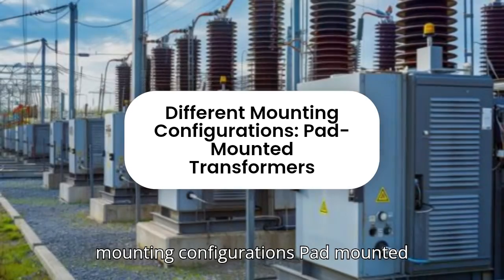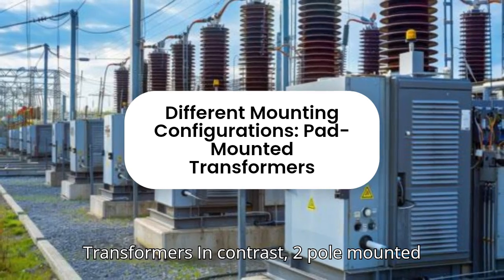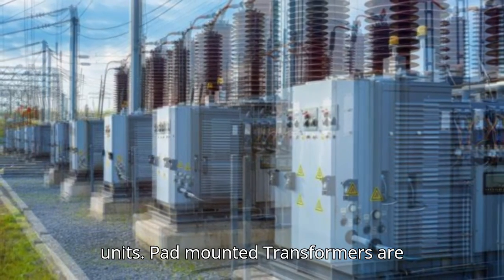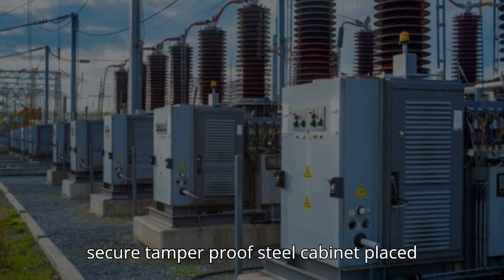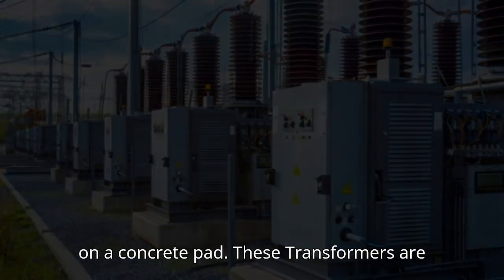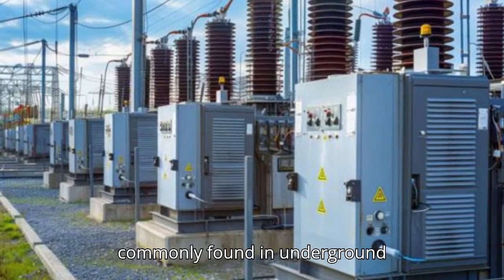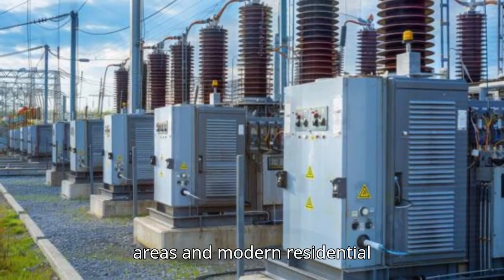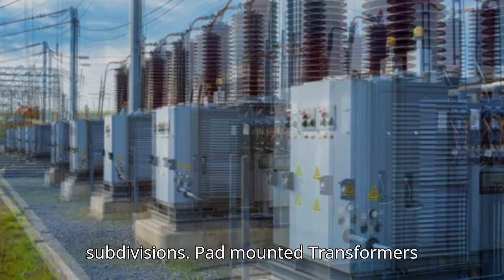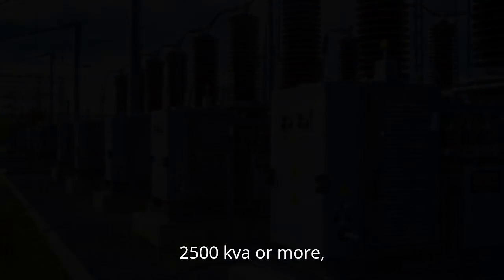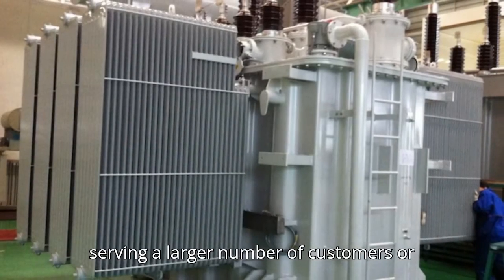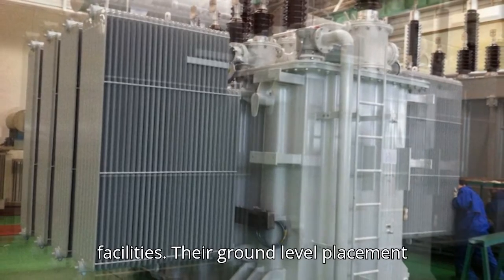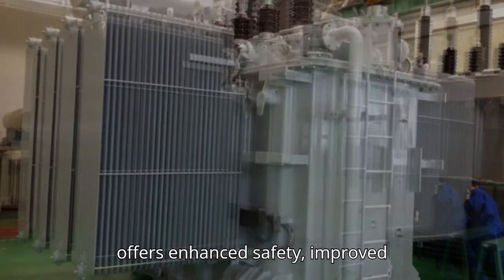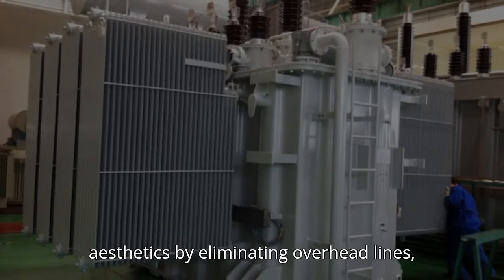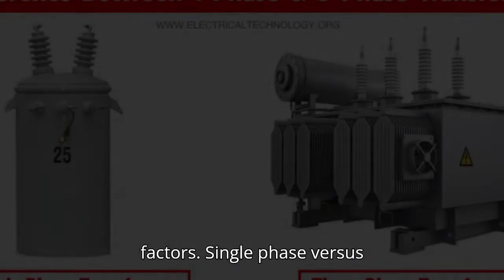Different mounting configurations. Pad-mounted transformers. In contrast to pole-mounted units, pad-mounted transformers are installed on the ground, enclosed in a secure, tamper-proof steel cabinet placed on a concrete pad. These transformers are commonly found in underground distribution systems prevalent in urban areas and modern residential subdivisions. Pad-mounted transformers are generally larger three-phase units, ranging from 75 kVA to 2,500 kVA or more, serving a larger number of customers or larger commercial and industrial facilities. Their ground-level placement offers enhanced safety, improved aesthetics by eliminating overhead lines, and better protection from environmental factors.